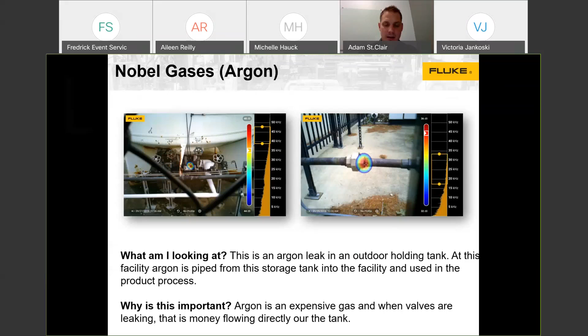And so this company used a whole lot of argon, and it was one of the biggest cost pieces of their production process in their facility. And so when we were able to go out and identify the different argon leaks and fix all of those, it increased their profitability for their output or what they were manufacturing considerably. This is 2 examples of the 10 different argon leaks we found from storage tank to where it goes into their production process. So that was direct cost savings, not energy savings, but still a pretty significant result for them in improving their bottom line. And this is, again, just an example that it's not just compressed air. It's a sound map, regardless of what's causing that sound.